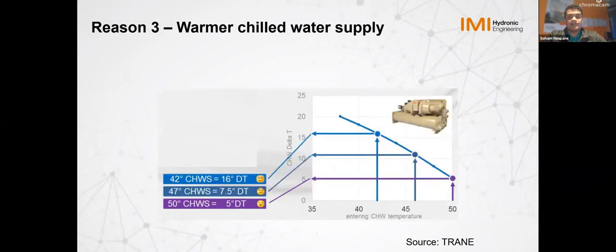Similarly, the third reason for a delta T issue is warm chilled water supply. And this is a pretty common issue too. Again, it is a general notion that if I change my set point of the chiller, just make it a little higher, I'm going to save some energy. But that's not exactly what happens. When you start changing it, you basically start warming the chilled water supply. What happens? Initially it was at 42 degrees with 16-degree delta T.